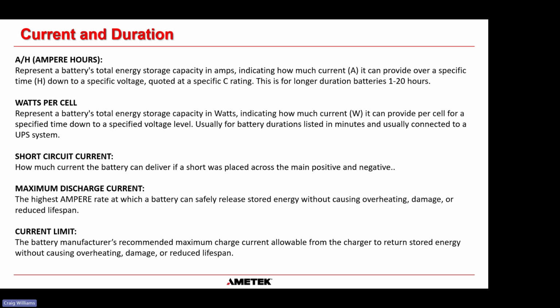For short duration batteries, they tend to use watts per cell, which represents a battery's total energy storage capacity in watts. It indicates how much power it can provide per cell for a specified time down to a specified voltage level. Watts per cell is usually used for battery durations listed in minutes, and is typically connected to UPS systems in high-powered data centers.